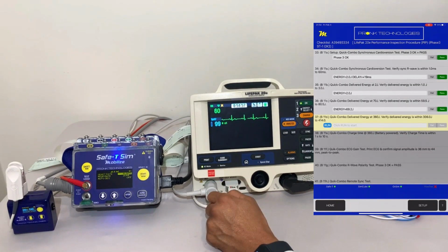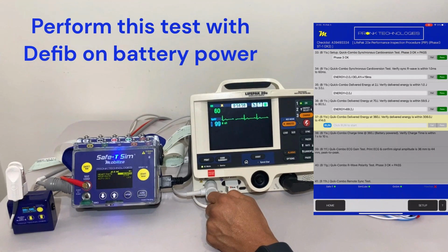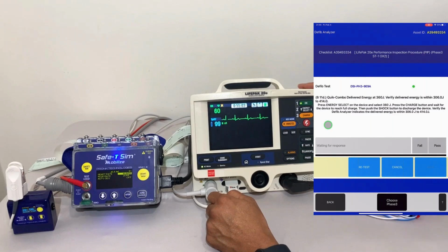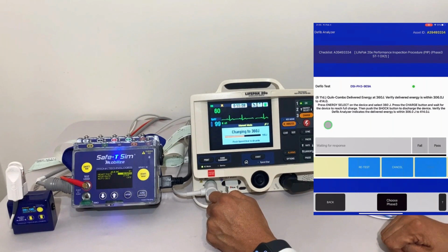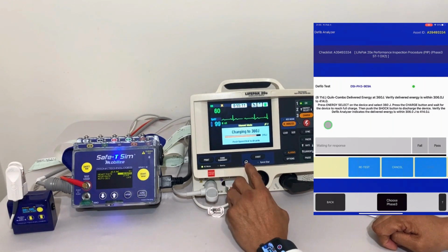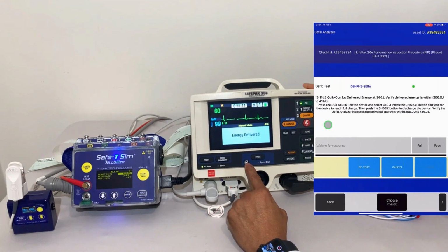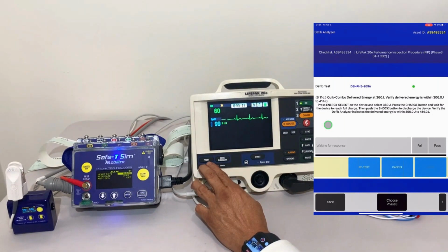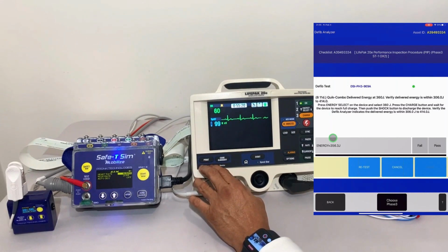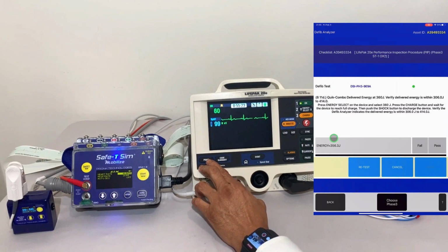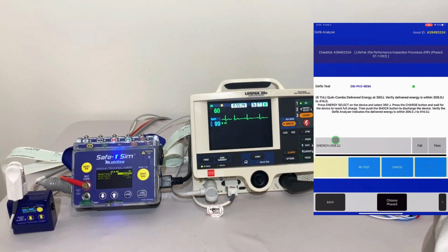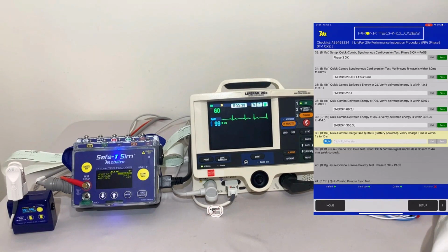So we're going to follow with the last discharge test, which is 360 joules. Let's go ahead and run that. That means charging the defibrillator to 360 joules, which we've had it set up here. Let's charge it. Printer starts to print. We're going to verify that the result we get back from the analyzer is within range. And we can see here that on a target of 360, we receive the result back from the defib analyzer of 356.3. The range is 306 to 414, so it is well within range. This is a pass.